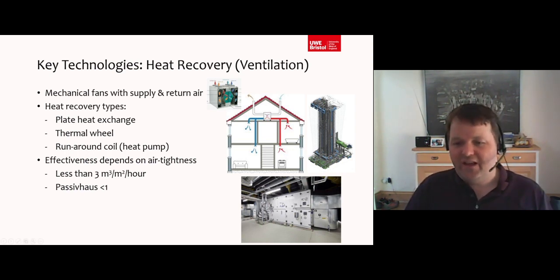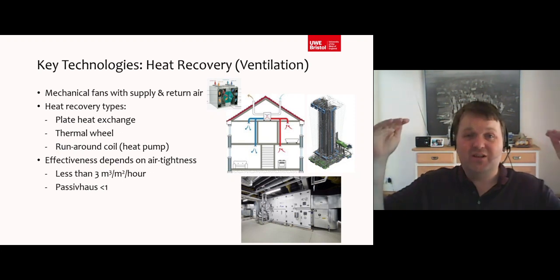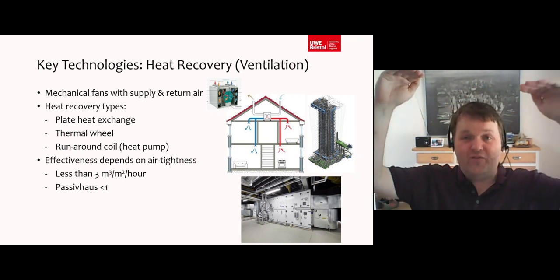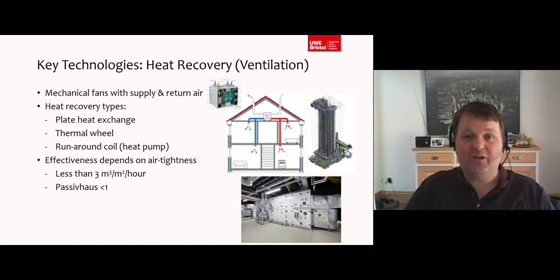And so the amount of heat, you see the tubes going in here, that's pumping in heat during the winter, and it's pumping in coolant during the summer, and it may even have to pump in both heating and cooling when it's doing full air conditioning, because to limit humidity, you have to cool right down to 12 degrees so that it drops all its moisture, and then warm back up again to comfort 18 degrees. And so that's why air conditioning, where humidity control is a point, is even more energy intensive, because you have to both cool and heat in order to condition that air.